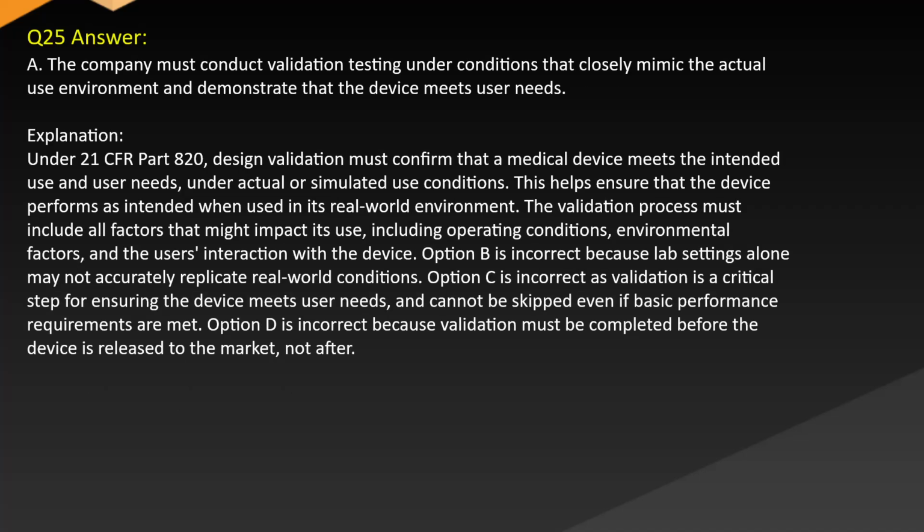Answer A. The company must conduct validation testing under conditions that closely mimic the actual use environment and demonstrate that the device meets user needs. Explanation: under 21 CFR Part 820, design validation must confirm that a medical device meets the intended use and user needs under actual or simulated use conditions. This helps ensure that the device performs as intended when used in the real-world environment. The validation process must include all factors that might impact its use, including operating conditions, environmental factors, and the user's interaction with the device.